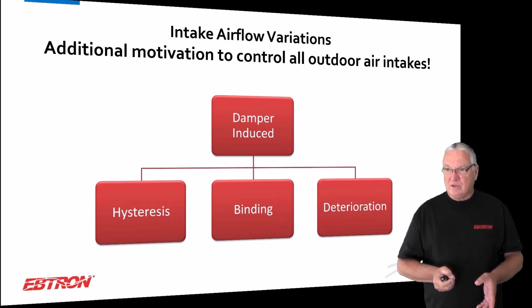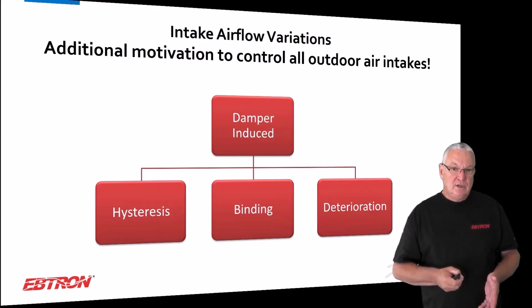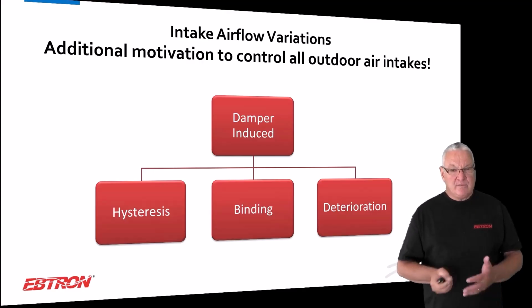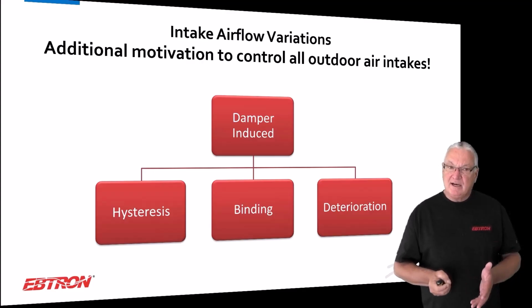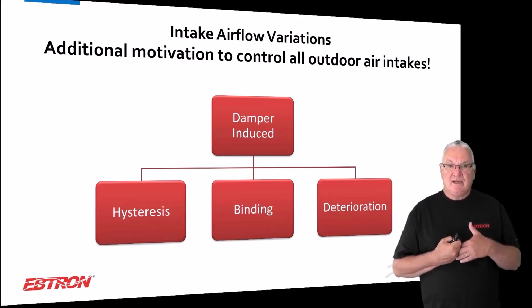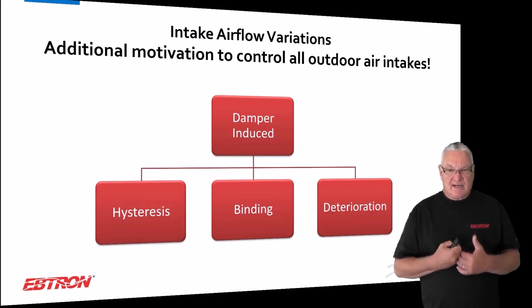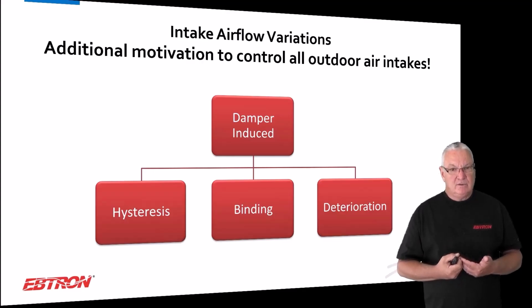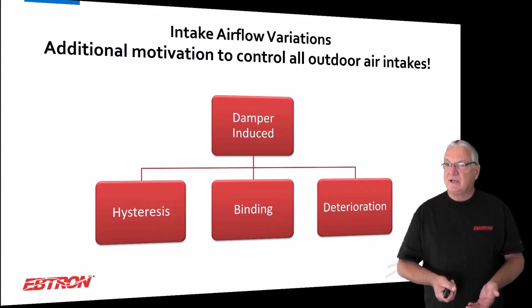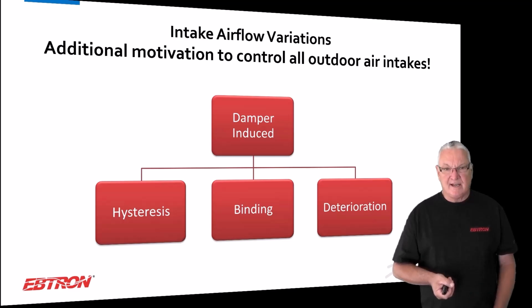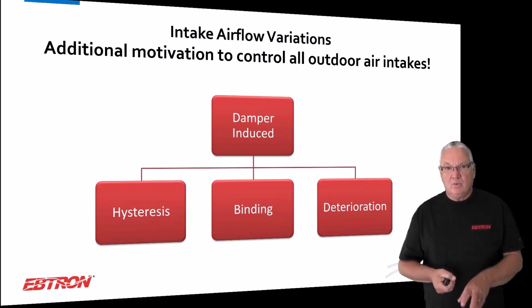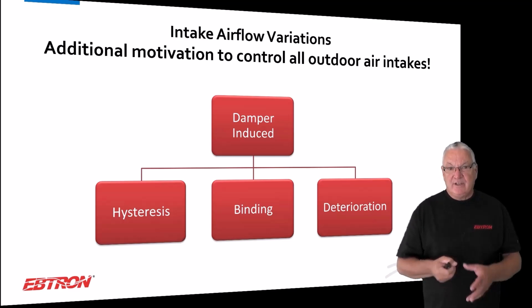Binding's pretty straightforward. Linkage binds, if you are going by straight damper position, and it can bind enough to break linkage. I've seen systems in my career where the actuator feedback looks good, my damper is supposed to be at this position, and it is. Then you go look at the damper, and the linkage is broken, and a couple of blades are hanging in the wind. You have no way to know what the flow rate is. You feel good. You have a false sense of security that your feedback signal is telling you you're okay.